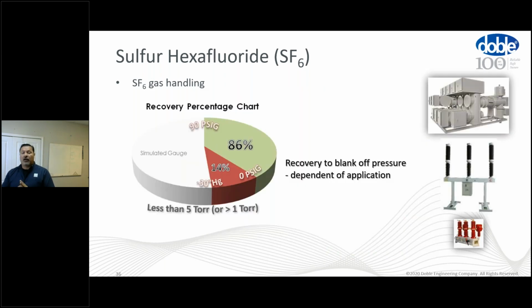So, recovery of gas. In this example, you see if we were to have a GIE at 90 psig and only recover to 0, we would only recover approximately 86% of the gas. 86%. That means that at least 14% may still be in the GIE. This is why we need to be sure that we have the right size of equipment, the right accessories to be able to recover 99.9 to 100% of the gas from that GIE compartment.